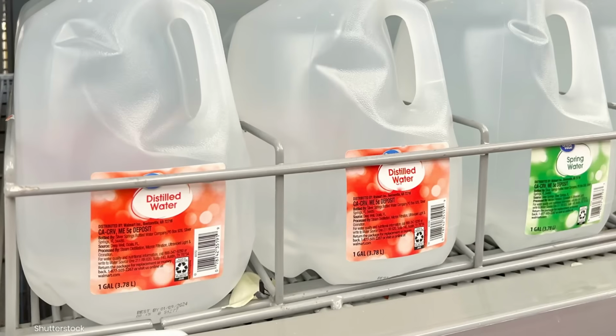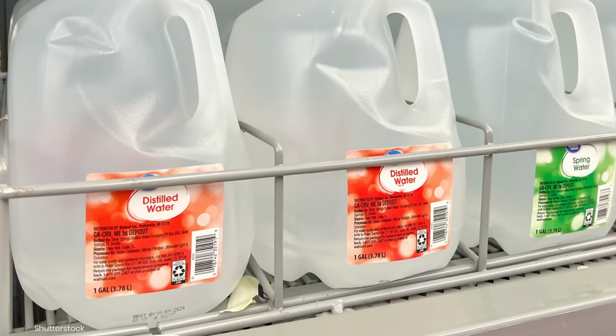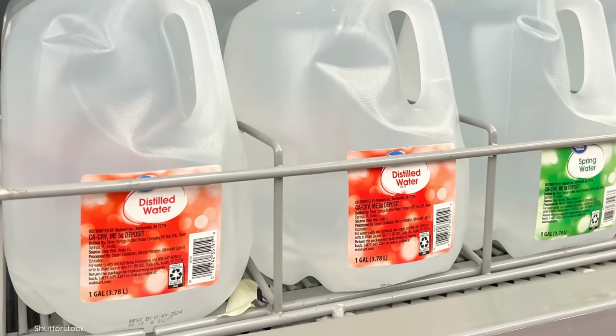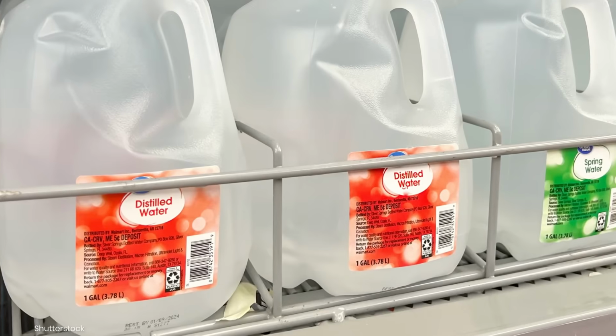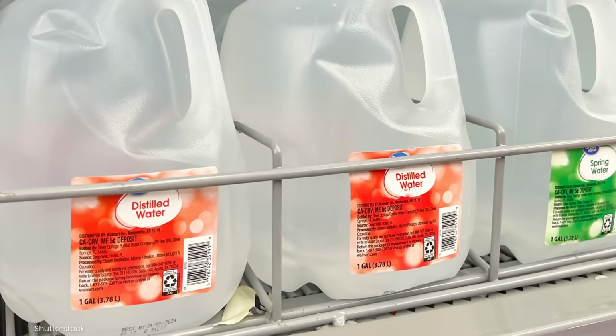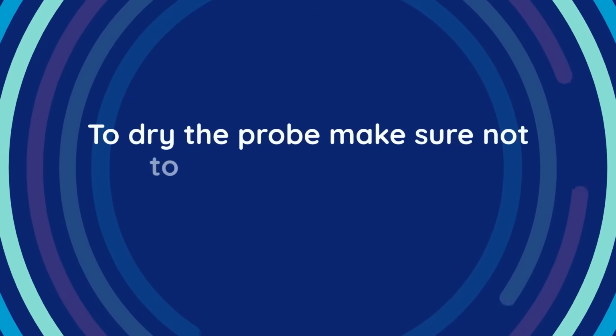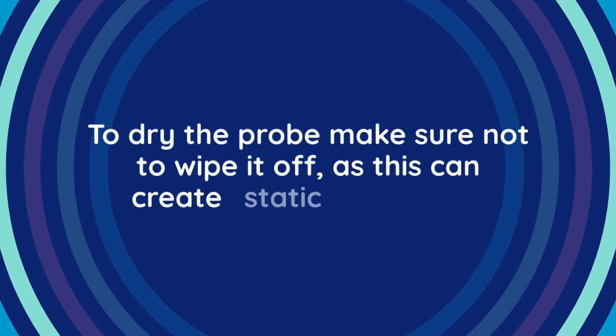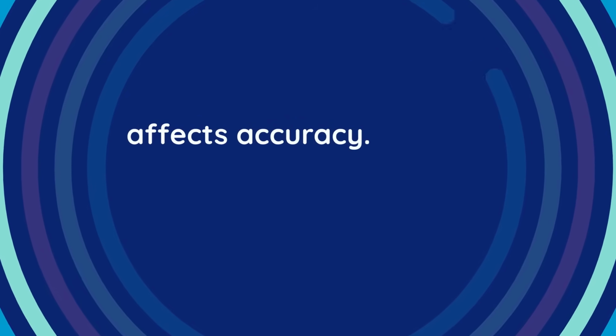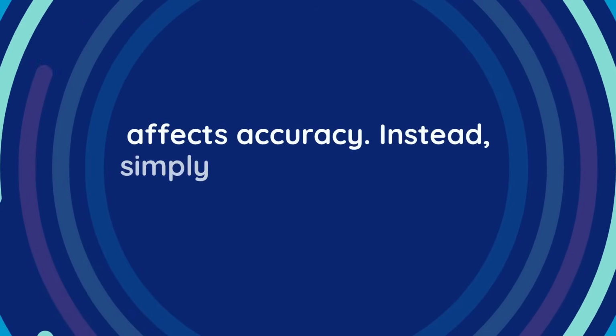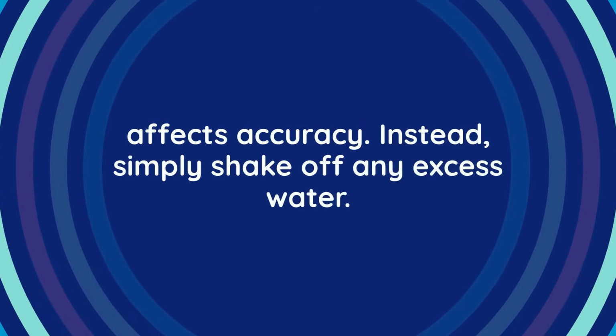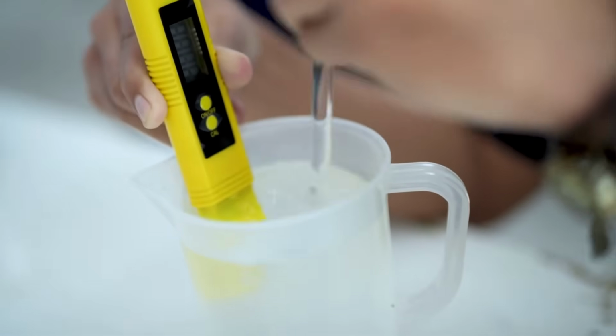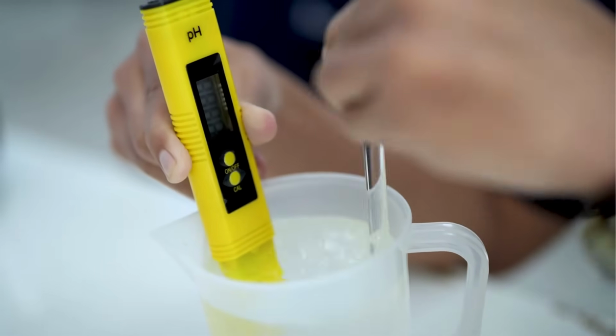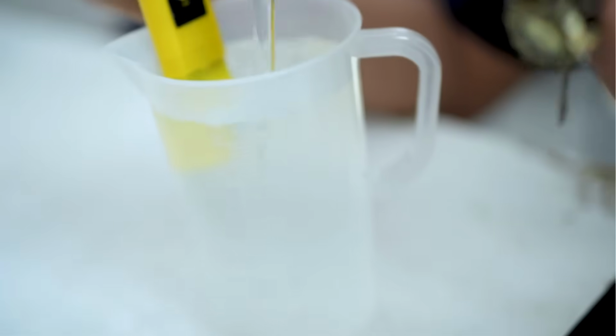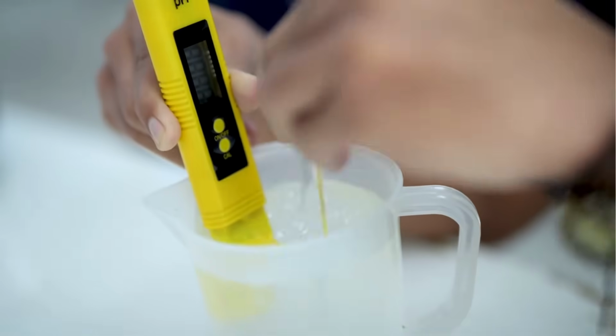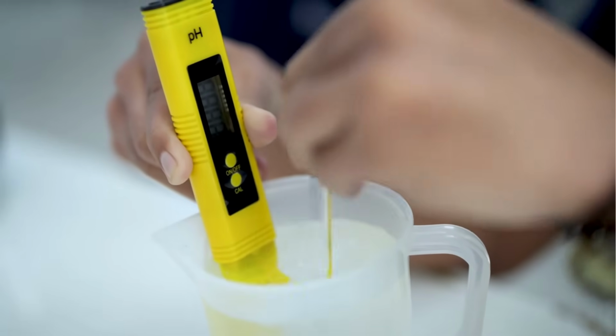pH. Before doing so, rinse the probe with distilled water to remove any residue from previous measurements, ensuring the readings won't be contaminated. To dry the probe, make sure not to wipe it off, as this can create static buildup that affects accuracy. Instead, simply shake off any excess water. Next, submerge the probe in the buffer solution, ensuring the sensitive tip is fully covered, and follow the meter's instructions to adjust it to the solution's specified pH value.